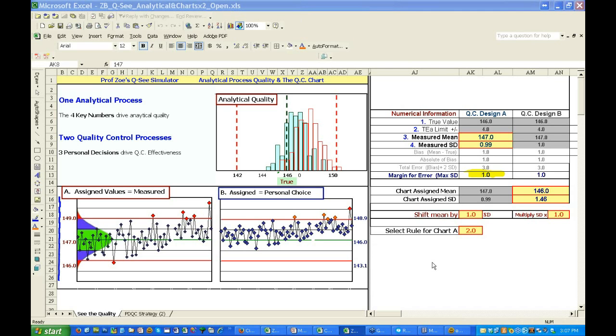Okay. Another question. When we look at quality control, there's sort of an assumption in the background that if a shift occurs, it's going to be a similar shift at both levels. We use the same control rules for the same sample. And when you're picking and choosing rules, we work with an N of 2 or 3. But have you seen examples where one level shifts, the high level shifts and the low level doesn't, or the low level drops out of sight and nothing happens to the high level?